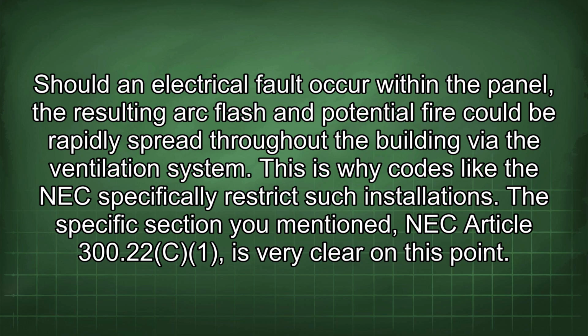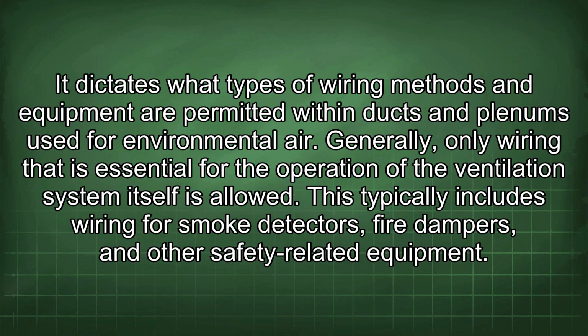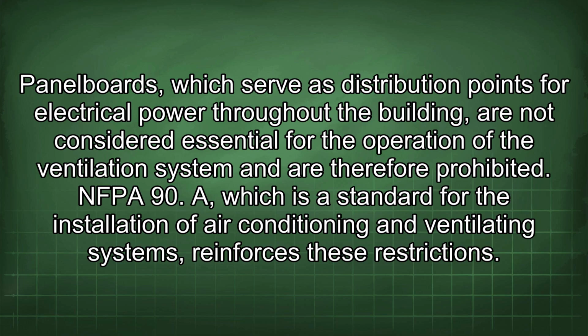This is why codes like the NEC specifically restrict such installations. The specific section you mentioned, NEC Article 300.22(C), is very clear on this point. It dictates what types of wiring methods and equipment are permitted within ducts and plenums used for environmental air. Generally, only wiring that is essential for the operation of the ventilation system itself is allowed. This typically includes wiring for smoke detectors, fire dampers, and other safety-related equipment. Panelboards, which serve as distribution points for electrical power throughout the building, are not considered essential for the operation of the ventilation system and are therefore prohibited.